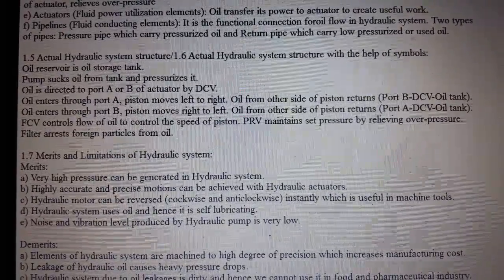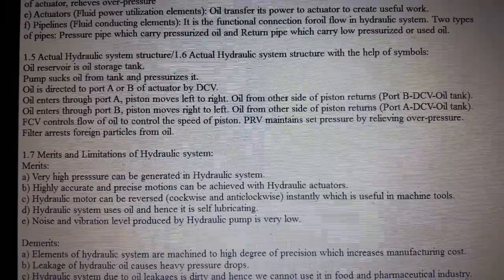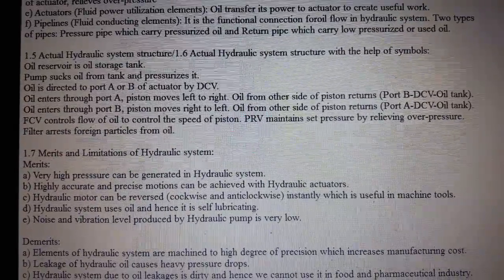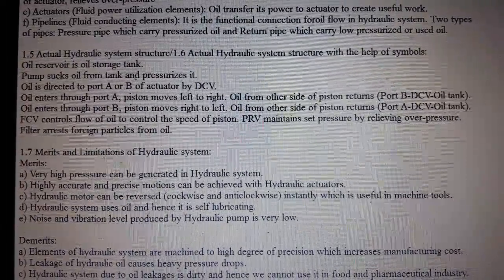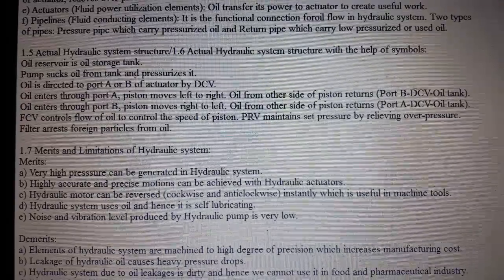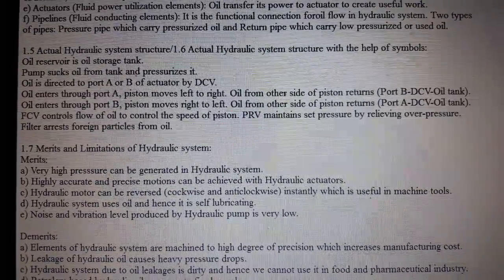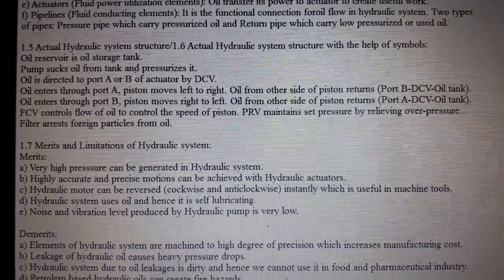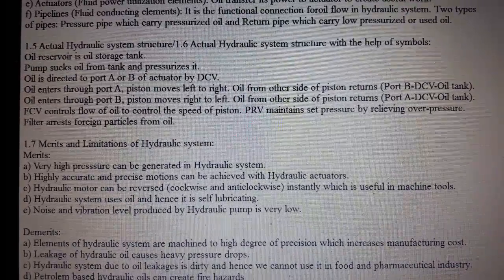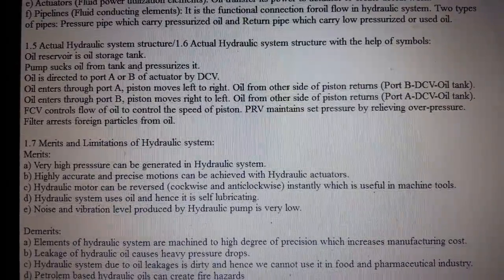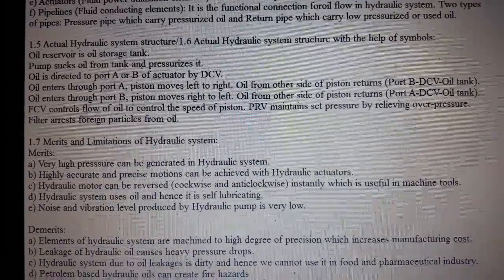When oil enters through port B, the piston moves from right to left. Oil from the other side of the piston returns through port A, then through the DCV, then to the oil tank. The FCV controls the flow of oil to control the speed of the piston. The PRV maintains the set pressure by relieving overpressure. The filter arrests foreign particles from the oil.